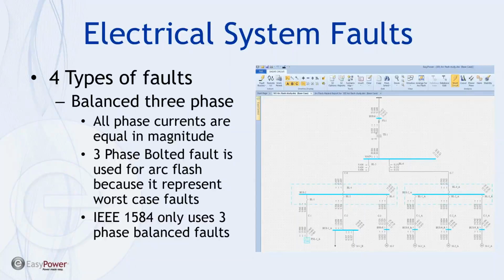And so specifically, there are four types of faults. First of which is a balanced three-phase fault, and by definition, all phase currents are equal in magnitude, and so again, it would be referred to as a symmetric fault. Three phases are bolted together because it represents a worst-case fault any system will see, and it's also the basis for the arc flash calculations that's reflected in IEEE 1584. And consequently, they only use the three-phase balanced fault because it is the worst case.